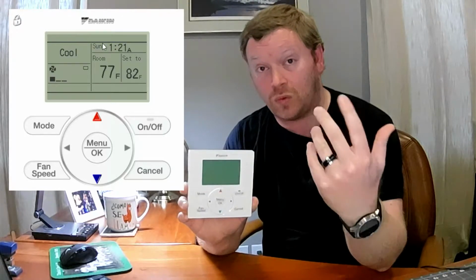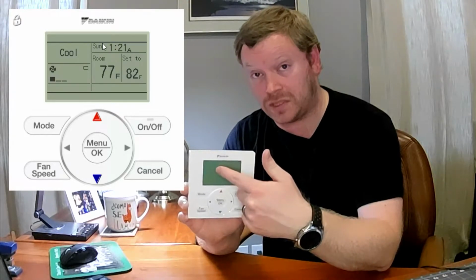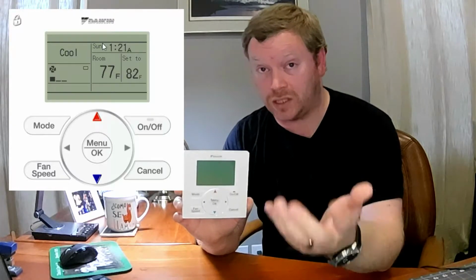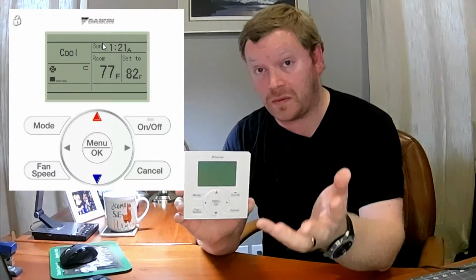Now, sometimes you might have a master controller that you don't want set as the master. Maybe there's a different NAV controller installed at your house or at your building or at your school, and you want that one to be the master. I'm going to show you very easily how to change the master NAV controller. First thing you're going to need to do is locate the current master. So the current master controller is the one that does not have an icon at the top that says master controlled. If you walk up to a NAV controller and at the top it says master controlled, that's not the master. You need to find the master.